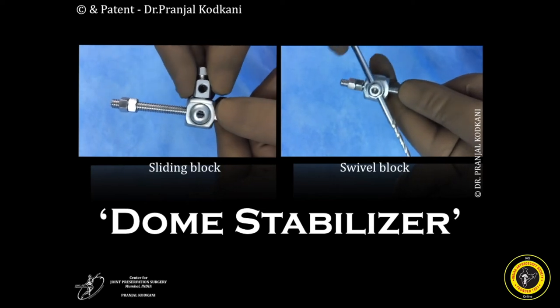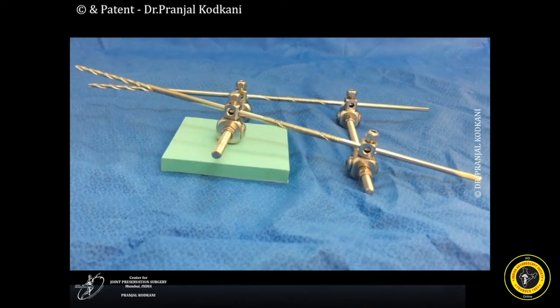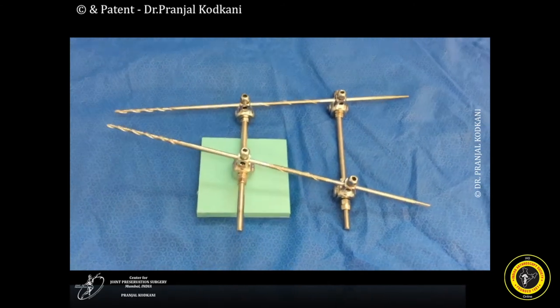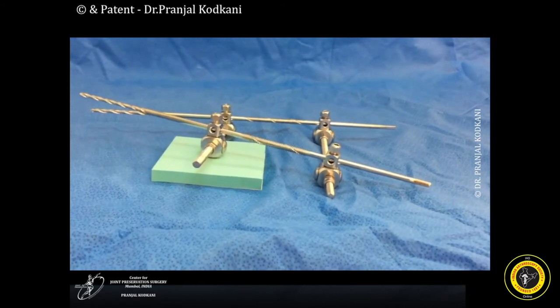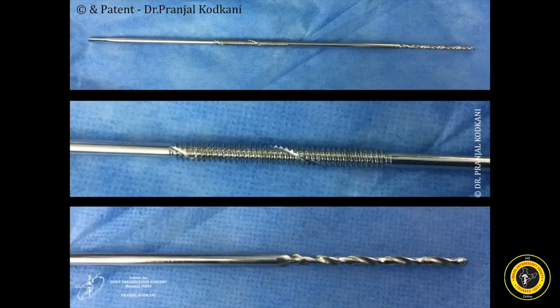Locking the swivel clamp does not affect the sliding mechanism of the fixator. The fixator allows both pins to be kept at an angle to each other not only in the coronal plane but also in the axial plane. This gives versatility to allow correction in both the coronal and axial planes, and to achieve a precise degree of correction without being restricted by parallel pins. This also allows post-operative alterations in correction if necessary. The pins used with the fixator are modified Denham pins with a self-tapping threaded central portion and a drill bit tip, allowing ease and precision in passing the pin using a drill rather than a T-handle.